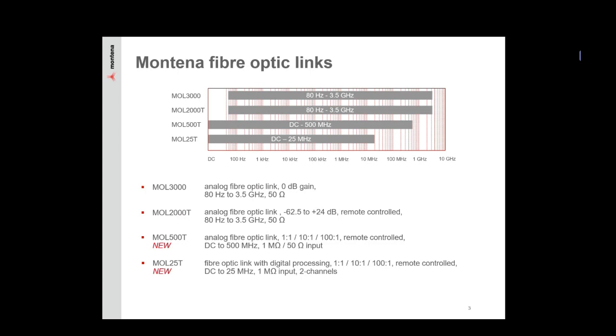The key with these last two is that they're very suitable as an oscilloscope front end or oscilloscope head. For very long distances, you have your oscilloscope head, which is the transmitter, and then up to half a kilometer or more of fiber optic cable back to the receiver and then to your oscilloscope. So all of these act as a measurement head in these environments, putting a good deal of distance between you and the control room, especially in hazardous areas or very strong electromagnetic fields.